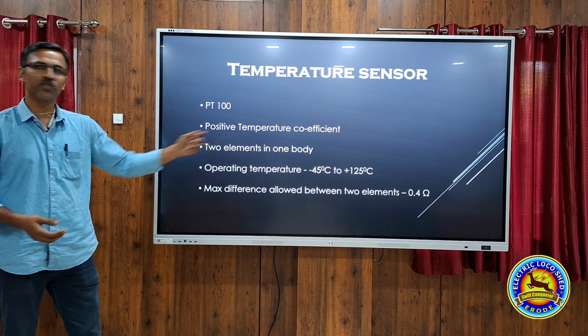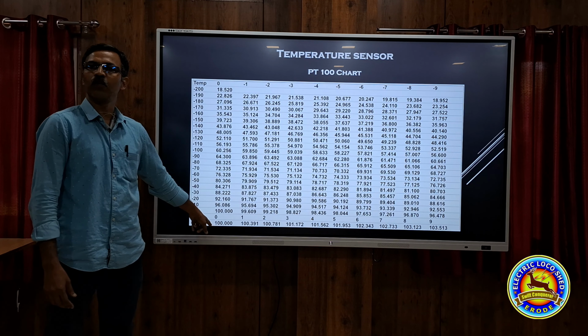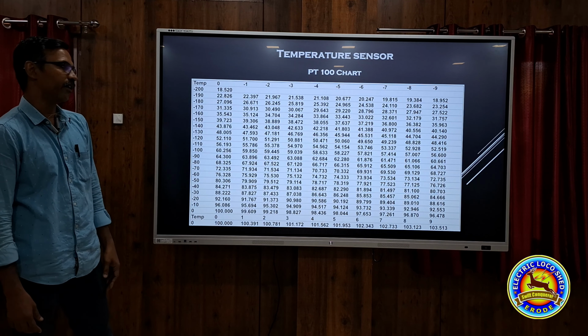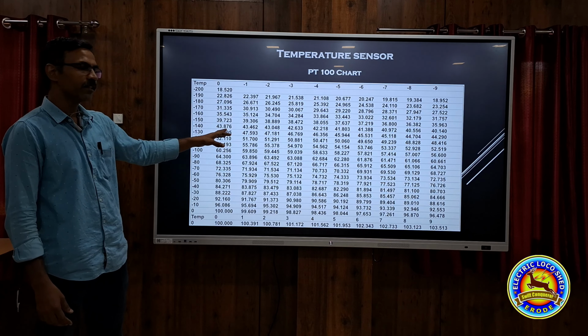As I said, there are two elements in a single sensor, so we can allow a maximum of 0.4 ohms difference between the two elements. This is the PT100 chart. Why is it called PT100? Because when the temperature is 0, the resistance will be 100 ohms. That is why it is called PT100. This is the PT100 chart.